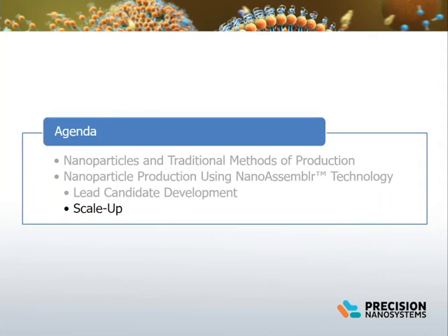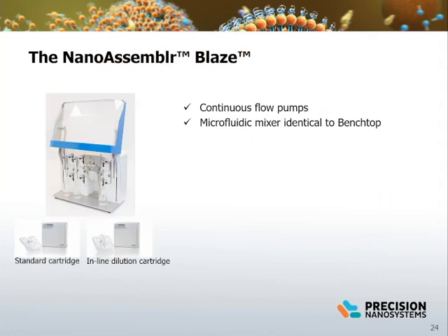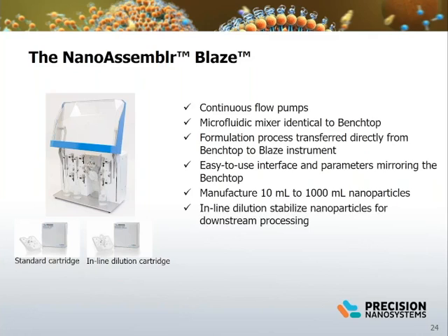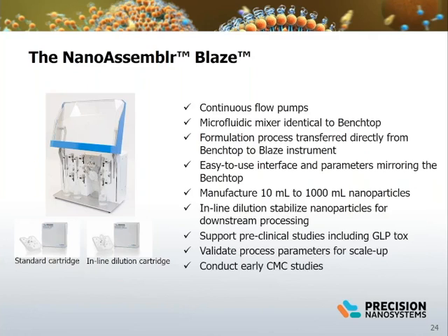With a robust formulation and manufacturing process established, the next step towards clinical manufacturing is scaling up. The NanoAssemblr platform makes the scale-up process relatively straightforward with direct transfer of manufacturing processes from the bench top to the Blaze instrument and scale-up system. The NanoAssemblr Blaze uses a continuous flow pumping system and the microfluidic mixing architecture is identical to the NanoAssemblr bench top. Formulation and manufacturing process parameters can be transferred directly using a software interface similar to the bench top, producing volumes up to one liter. Inline dilution is available as an option to stabilize the nanoparticles for downstream processing.